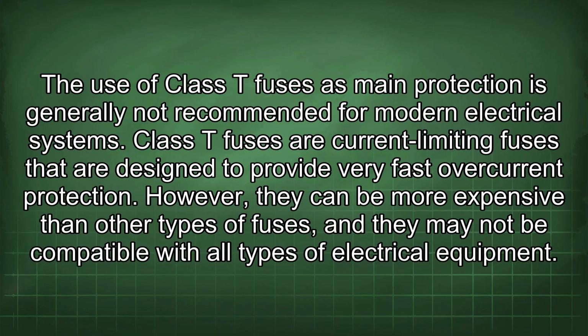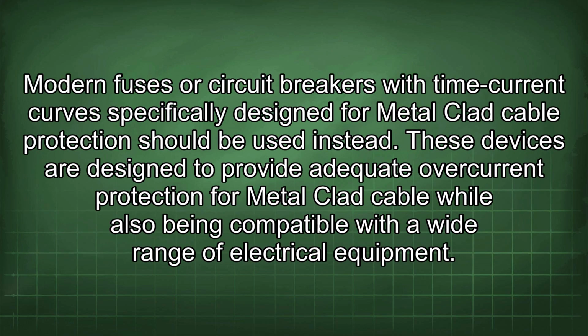of electrical equipment. Modern circuit breakers with time current curves specifically designed for metal-clad cable protection should be used instead. These devices are designed to provide adequate overcurrent protection for metal-clad cable while also being compatible with a wide range of electrical equipment.